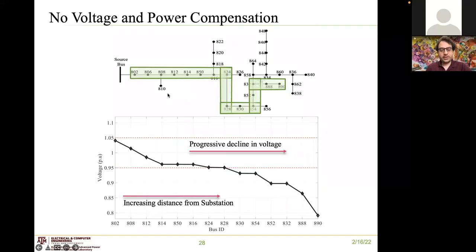If you take this feeder and do a power flow simulation, assuming the loads are at peak values, and determine the voltages at each of the load buses, here is the voltage plot. As we go away from the source bus, that is from the substation, we see a progressive decline in the voltages, and the buses shown in the shaded region are where these voltages fall.